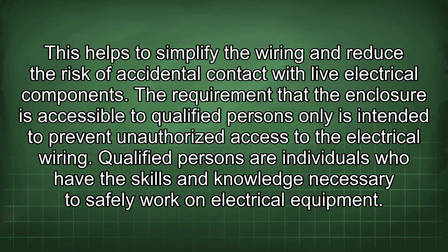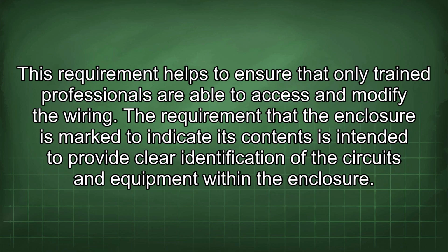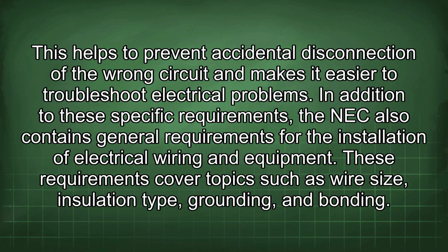The requirement that the enclosure is accessible to qualified persons only is intended to prevent unauthorized access to the electrical wiring. Qualified persons are individuals who have the skills and knowledge necessary to safely work on electrical equipment. This requirement helps to ensure that only trained professionals are able to access and modify the wiring. The requirement that the enclosure is marked to indicate its contents is intended to provide clear identification of the circuits and equipment within the enclosure. This helps to prevent accidental disconnection of the wrong circuit and makes it easier to troubleshoot electrical problems.